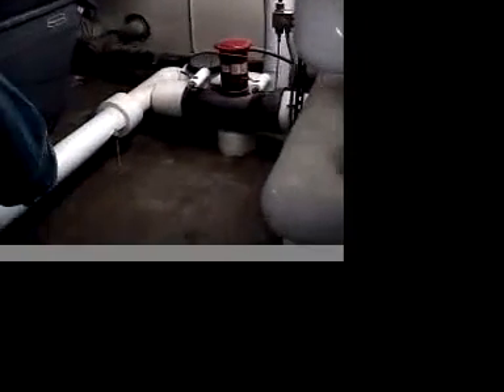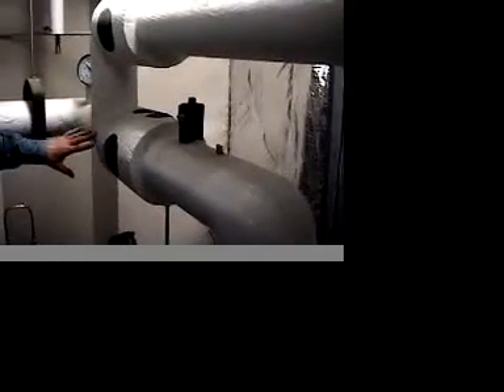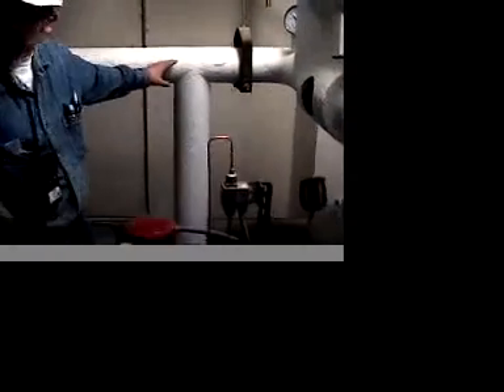Pretty much what you have here is your supply. You can kind of see the supply from the other side. It comes down through here, comes through the pump, goes into the air handler. There's a split coil in here, so there's two separate coils. It comes back, there's circuit setters here that are set, and you come back through here, and it goes back to the return through the control valve.